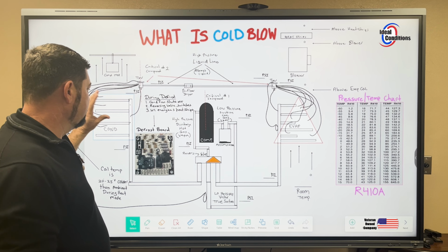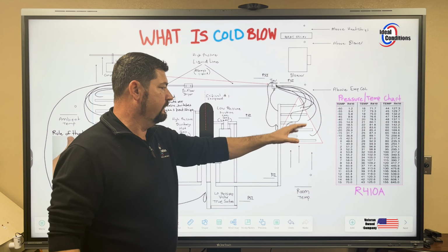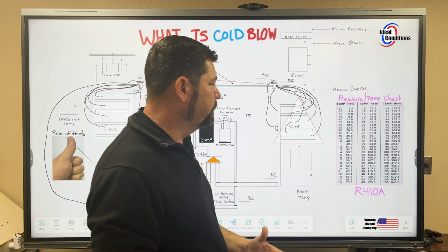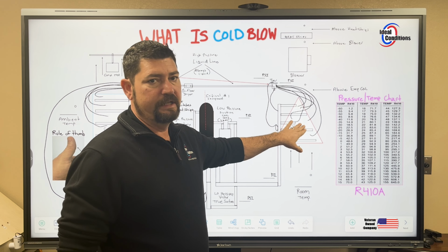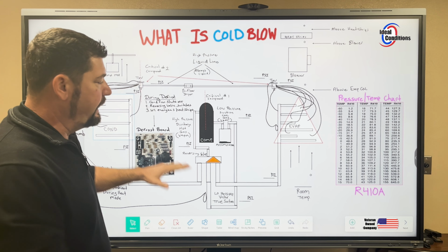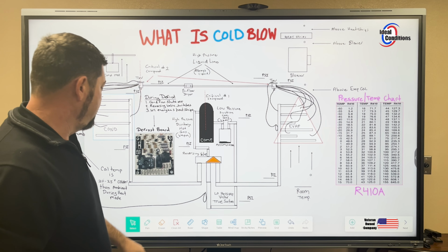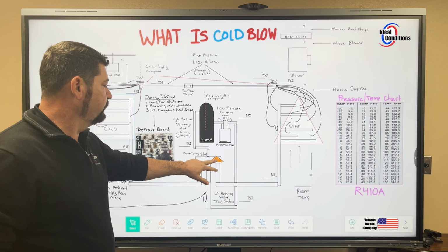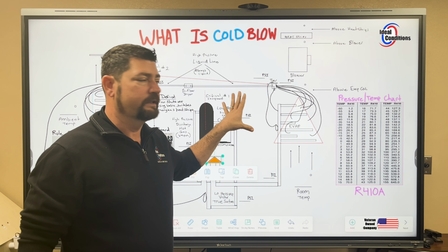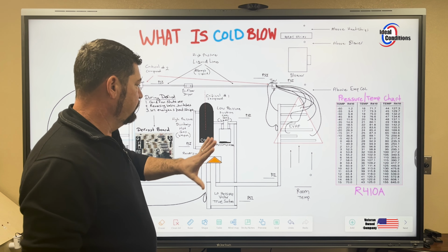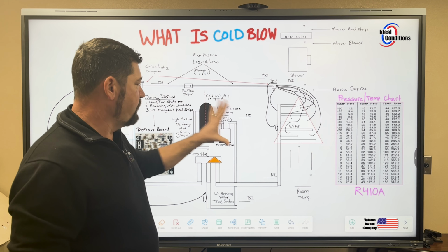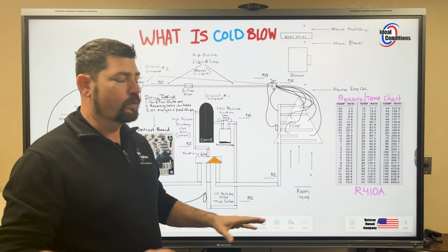So if you notice, the condenser coil is blank and the evaporator coil is blank. We're not using red or blue starting off. So what you need to think of, whether this is in heat or cool, at no matter what. Okay, it doesn't matter where my reversing valve is resting, whether it's in the heat mode or the cool mode, it does not matter. I will always be at these values. Okay, these values of liquid, the values of vapor. And so always refer back to this because I'm always in this state no matter what, heat or cool.